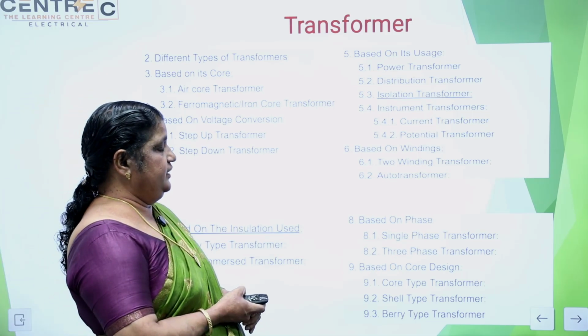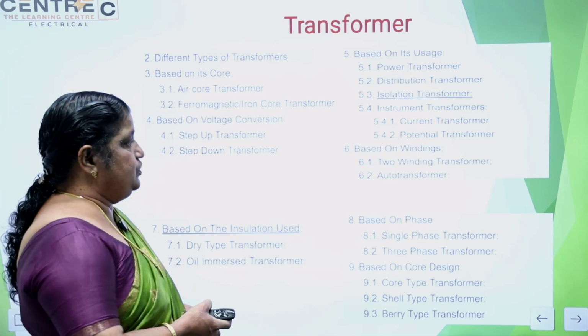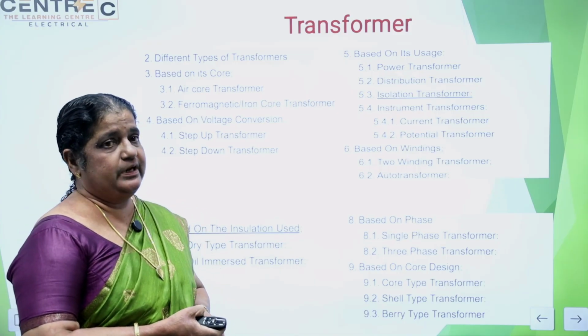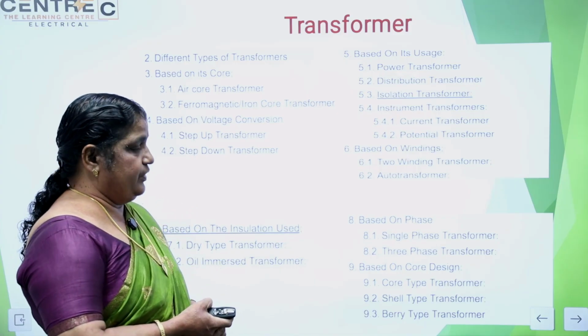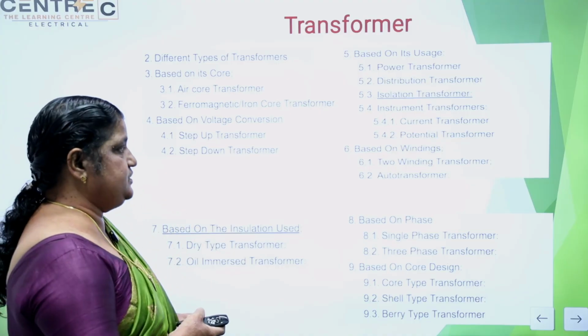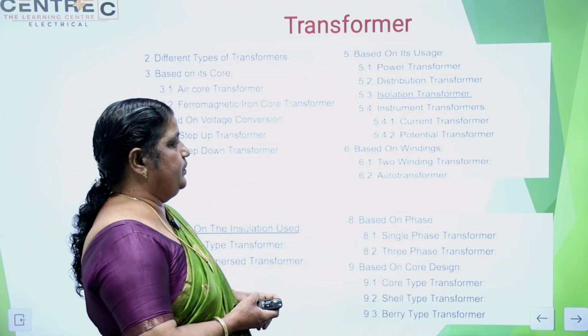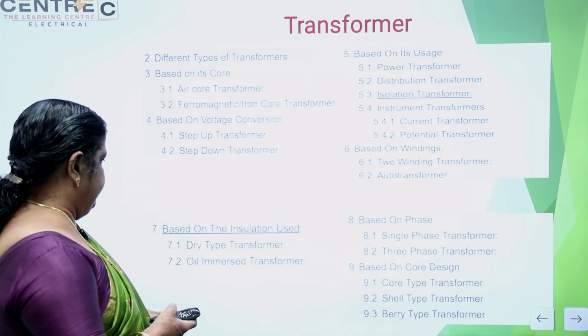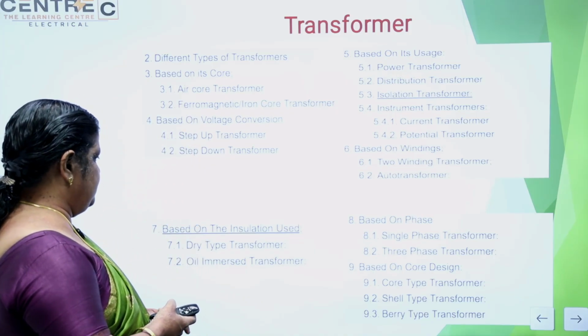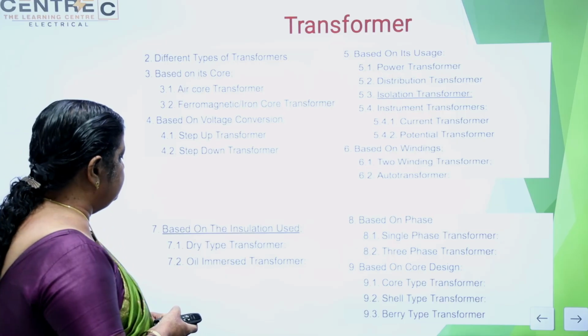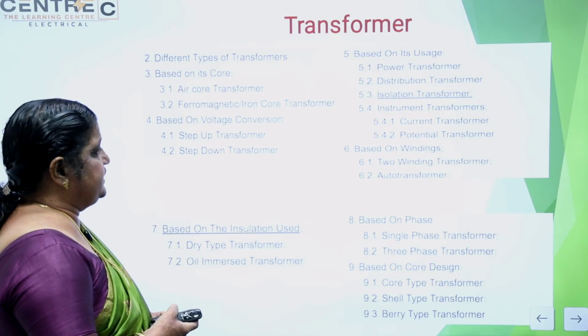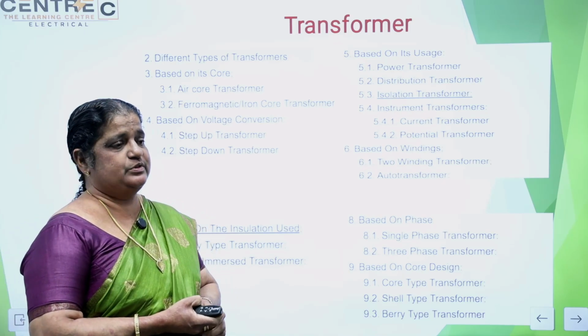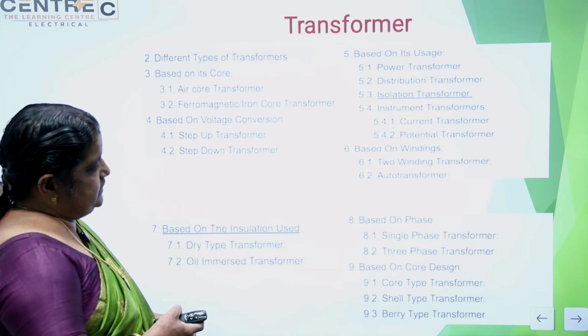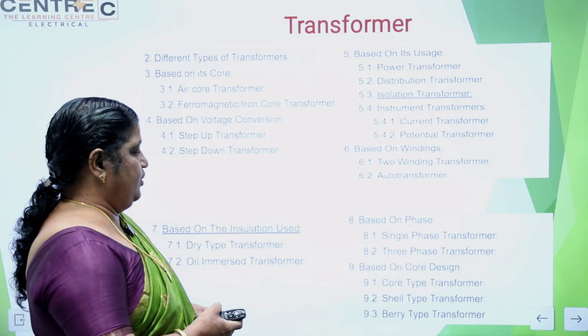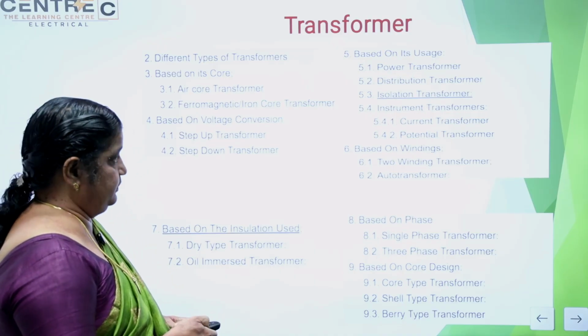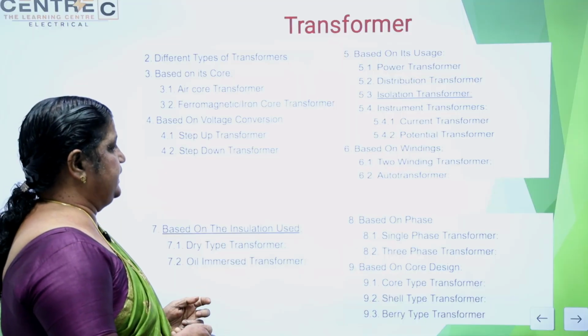Then based on the winding, transformers are divided into two winding transformer and auto transformer. In an auto transformer, only one winding is there, and a part of that winding is used as the secondary. A two winding transformer is normal, with one primary winding and one secondary winding. Then based on the insulation used, dry type and oil immersed transformer. Mainly power transformers and distribution transformers are oil immersed transformers. Then based on phase, single phase and three phase. Then core design: core type, shell type and berry type. Mainly we use the core type and shell type.